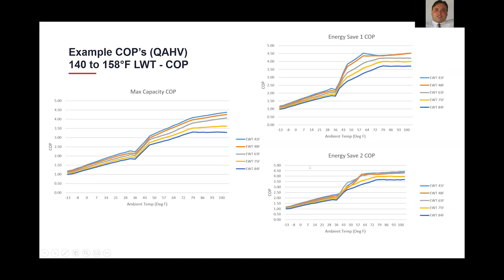And I'll show some of the differences of those in a minute. But you'll see between -13, where we chart down to upwards of over 100 degrees, you'll see you start out with a COP just slightly over 1, and then upwards of 4.5 at these higher ambient conditions. So there are some differences in shape here with COPs, but if you trend these lines, it's fairly consistent across these different operating modes.